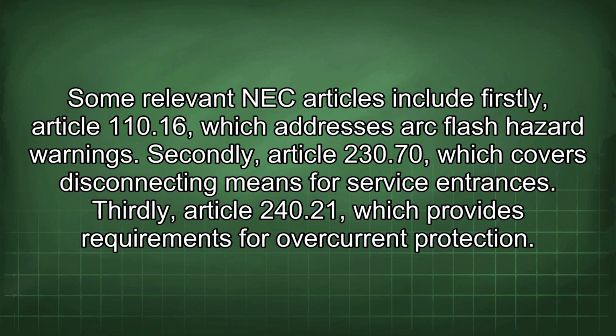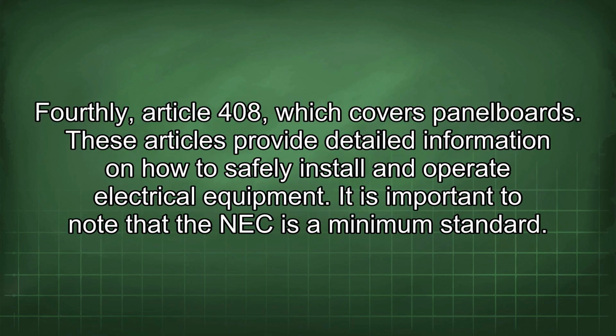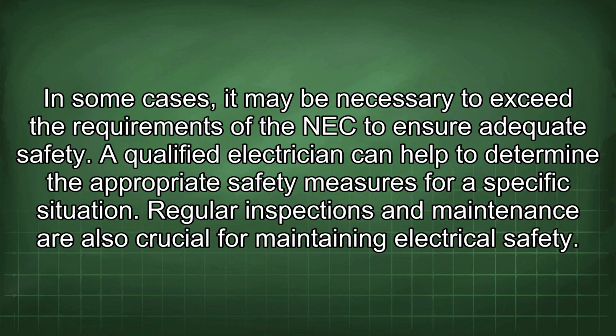Thirdly, Article 240.21, which provides requirements for overcurrent protection. Fourthly, Article 408, which covers panel boards. These articles provide detailed information on how to safely install and operate electrical equipment. It is important to note that the NEC is a minimum standard. In some cases, it may be necessary to exceed the requirements of the NEC to ensure adequate safety. A qualified electrician can help to determine the appropriate safety measures for a specific situation.